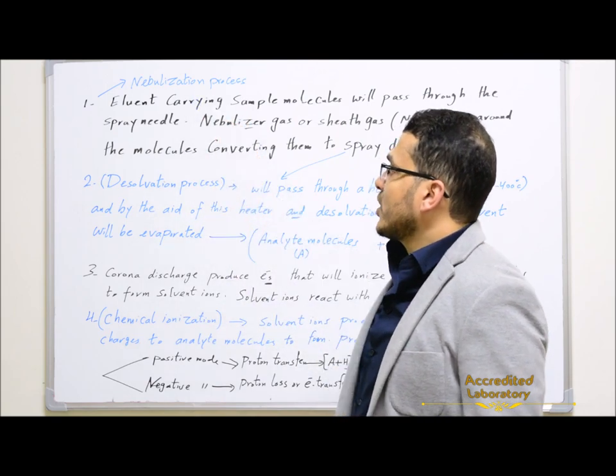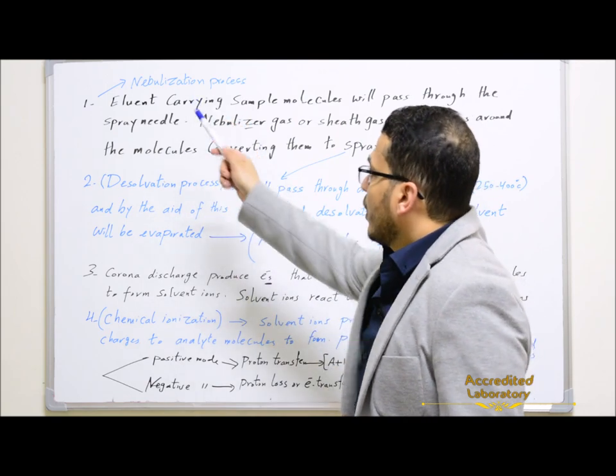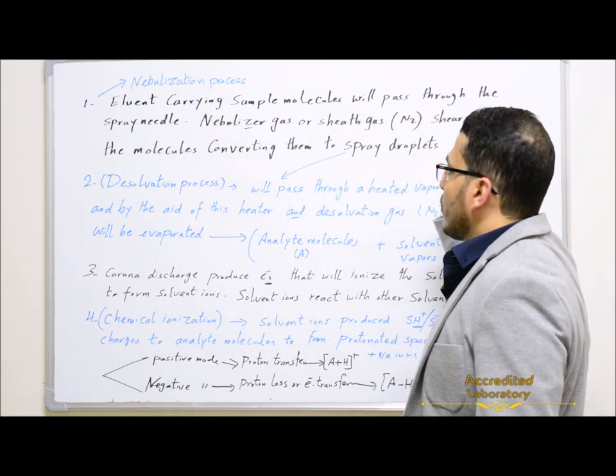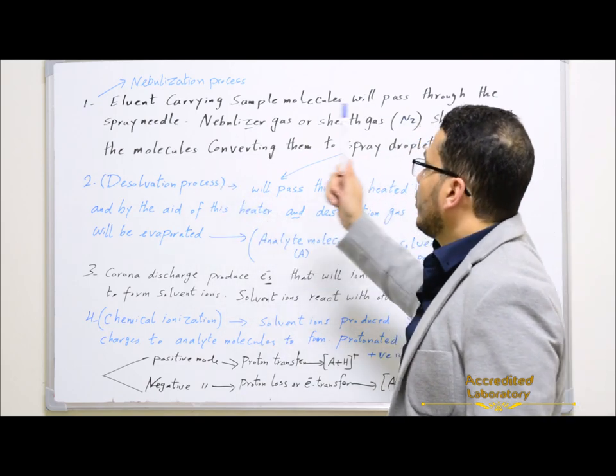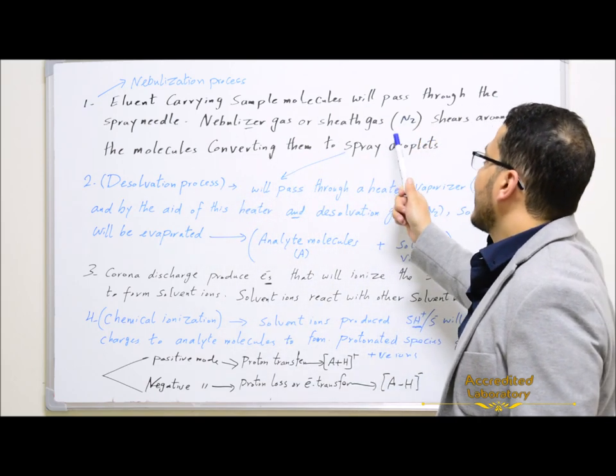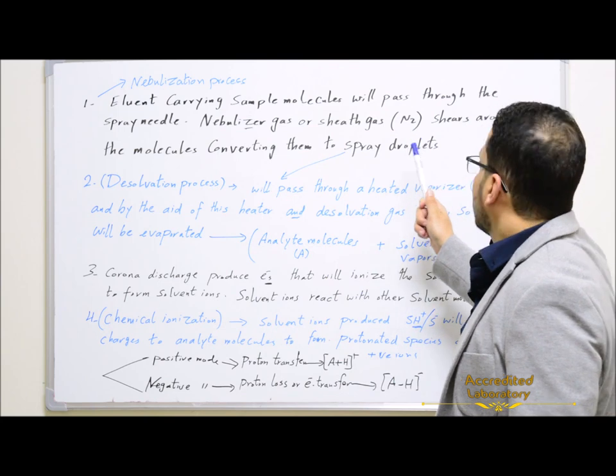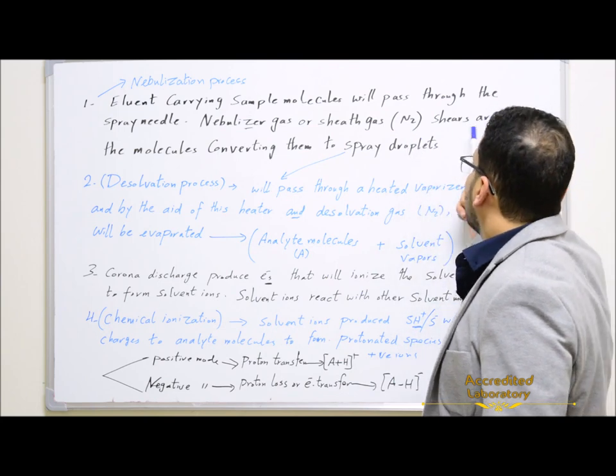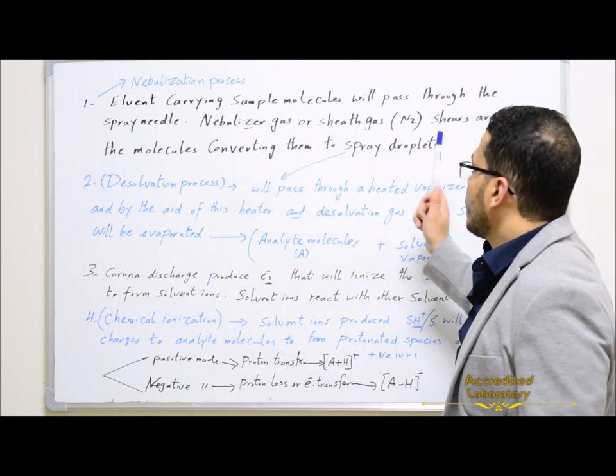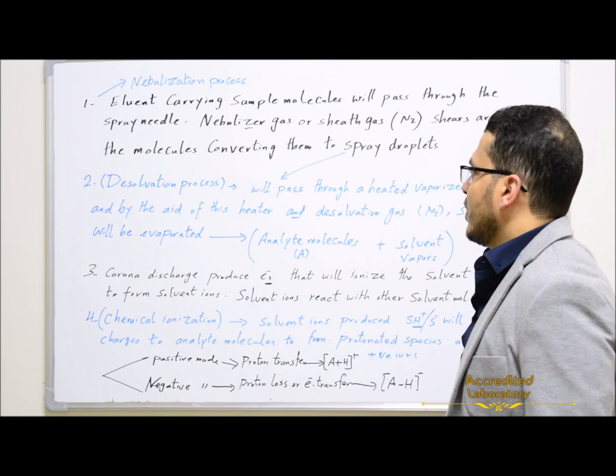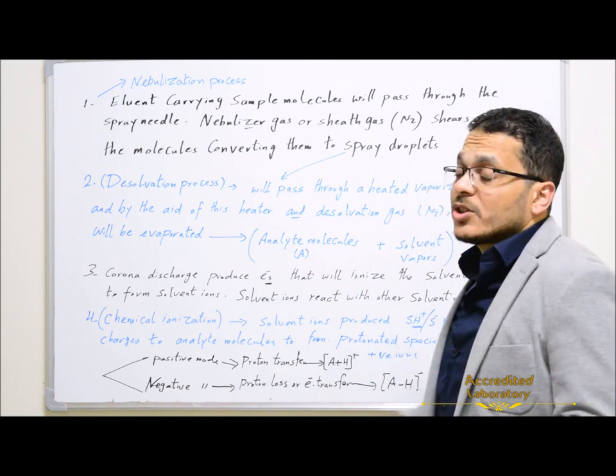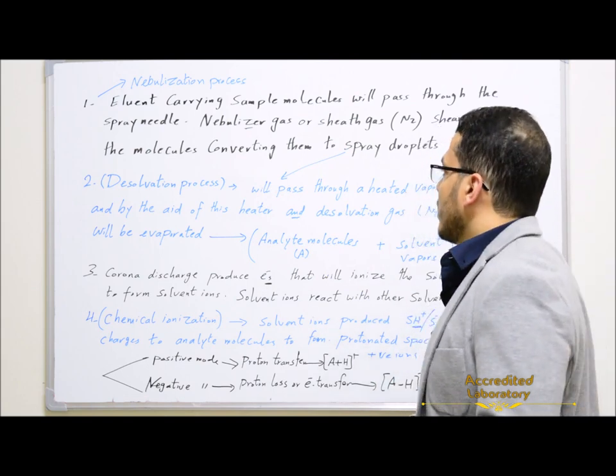Nebulization process: the eluent carrying sample molecules will pass through the spray needle. Nebulizer gas, or sheath gas, which is nitrogen gas, shears around the molecules, converting them to spray droplets which consist of sample molecules surrounded by solvent molecules.